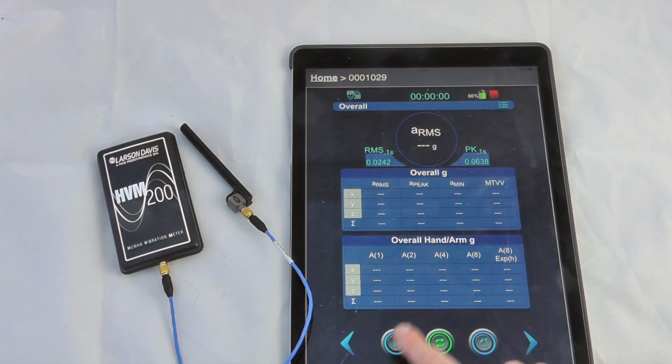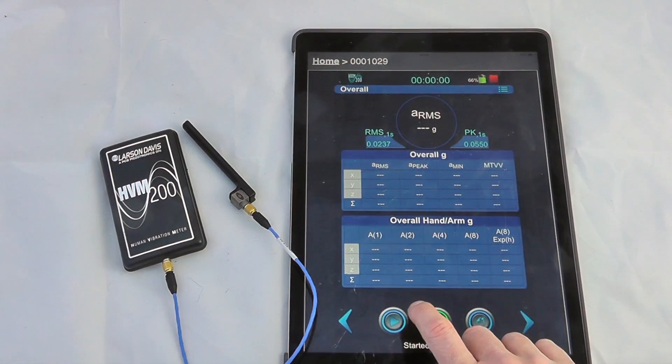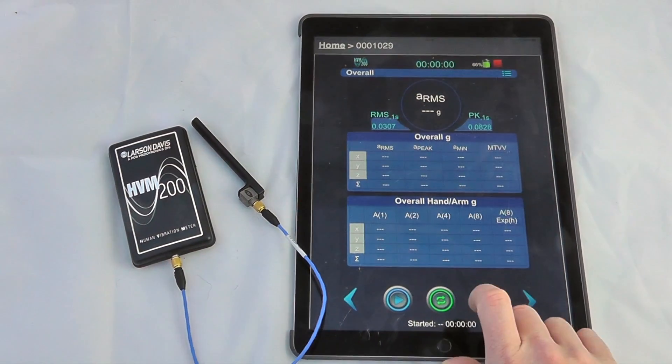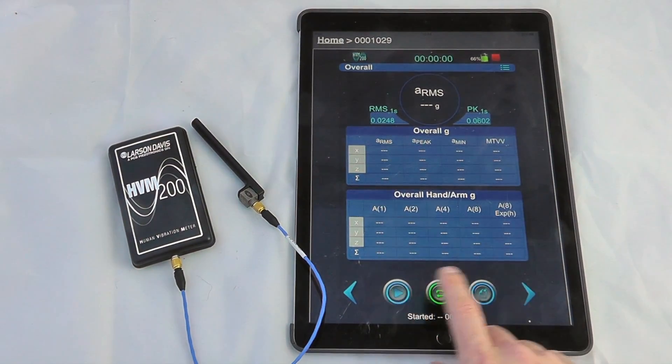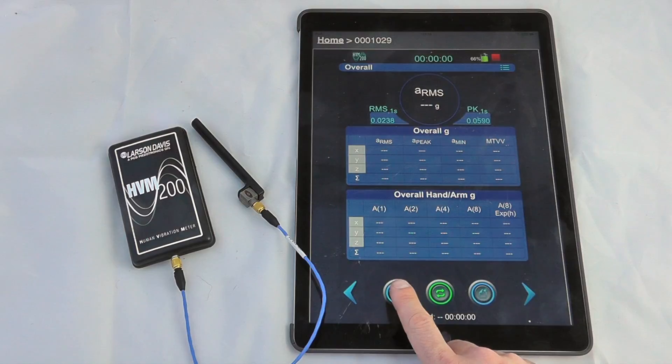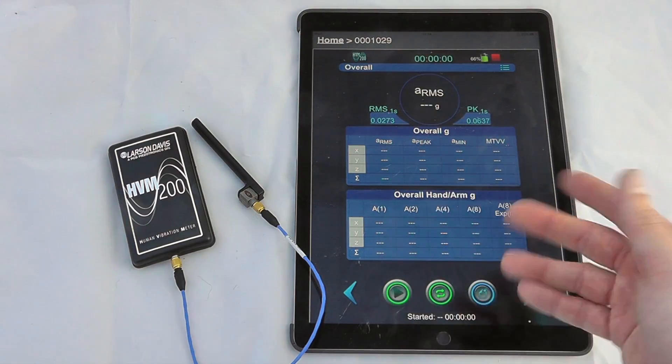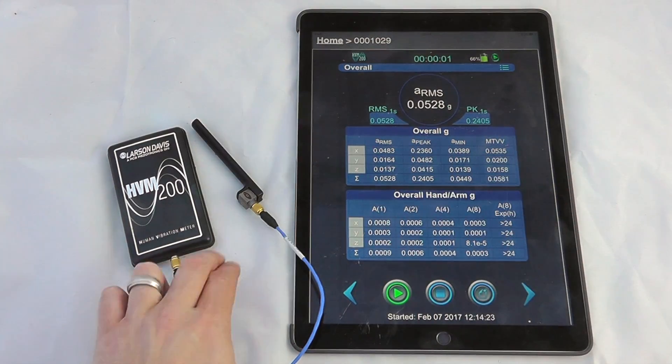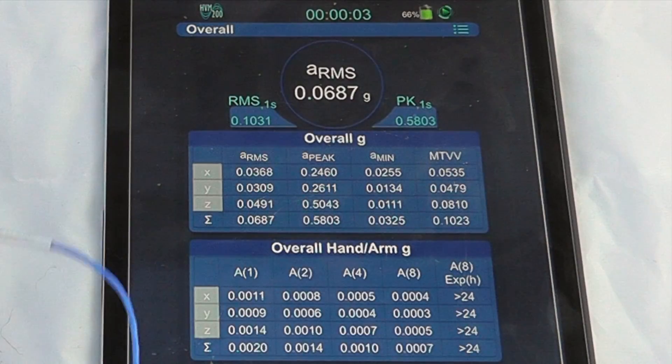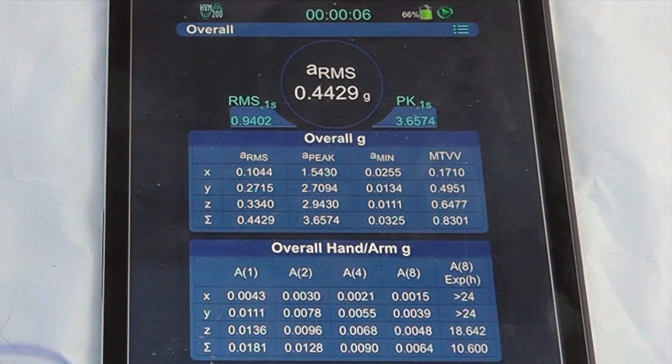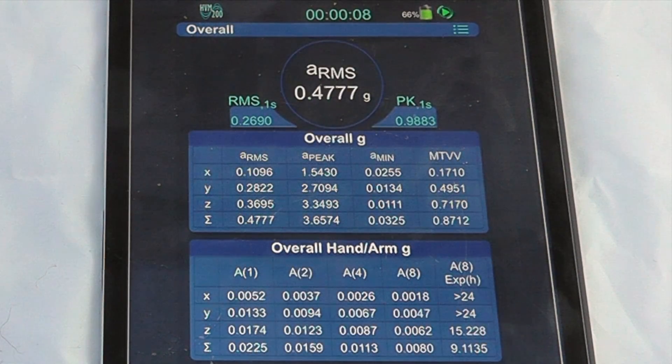But if I did want to start a measurement I'd press the play button down at the bottom here. It also gives me some general instrumentation settings. So if I press play I can begin a measurement with the device. We now see we're getting some vibration levels via the WiFi connection from the accelerometer here.